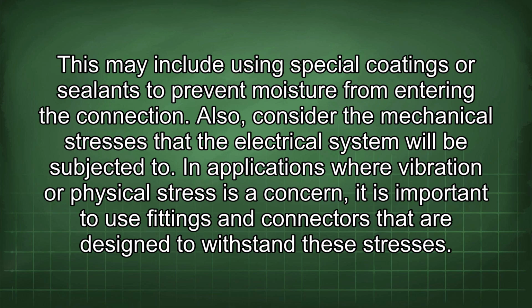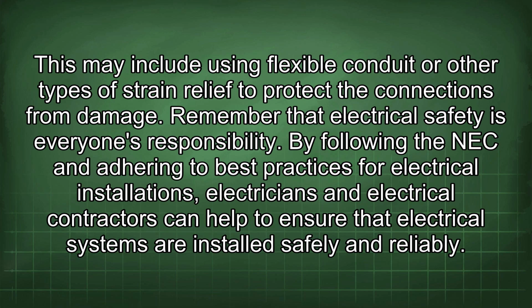Also, consider the mechanical stresses that the electrical system will be subjected to. In applications where vibration or physical stress is a concern, it is important to use fittings and connectors that are designed to withstand these stresses. This may include using flexible conduit or other types of strain relief to protect the connections from damage.